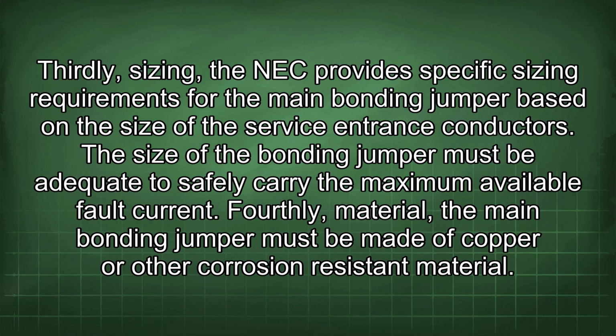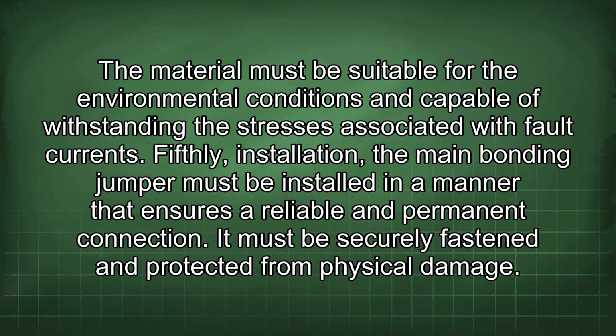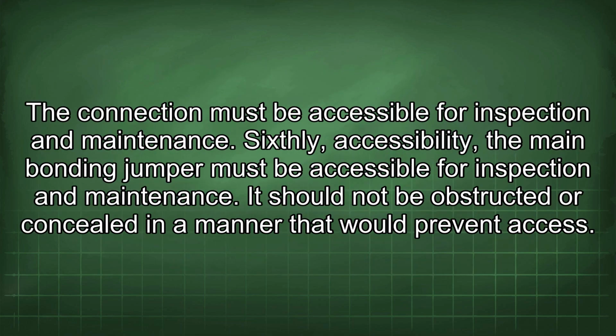Fourthly, material. The main bonding jumper must be made of copper or other corrosion-resistant material. The material must be suitable for the environmental conditions and capable of withstanding the stresses associated with fault currents. Fifthly, installation. The main bonding jumper must be installed in a manner that ensures a reliable and permanent connection. It must be securely fastened and protected from physical damage. The connection must be accessible for inspection and maintenance. Sixthly, accessibility. The main bonding jumper must be accessible for inspection and maintenance. It should not be obstructed or concealed in a manner that would prevent access.